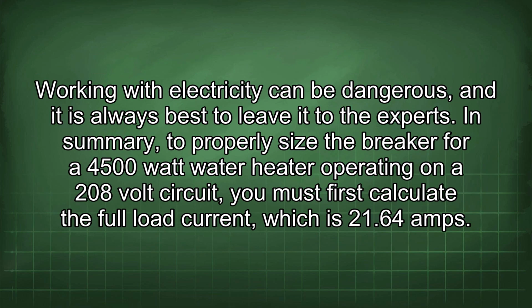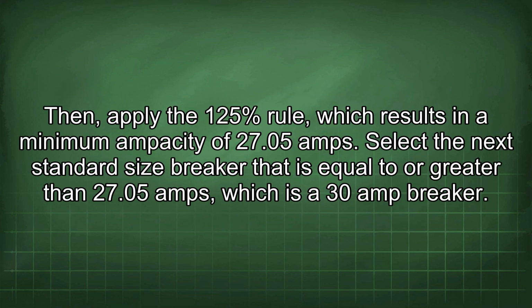Working with electricity can be dangerous, and it is always best to leave it to the experts. In summary, to properly size the breaker for a 4,500 watt water heater operating on a 208 volt circuit, you must first calculate the full load current, which is 21.64 amps. Then apply the 125% rule, which results in a minimum ampacity of 27.05 amps.